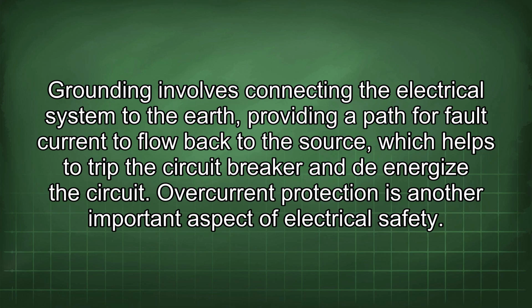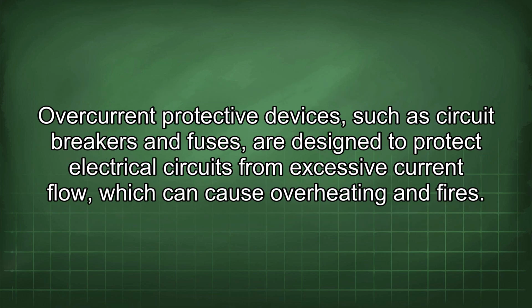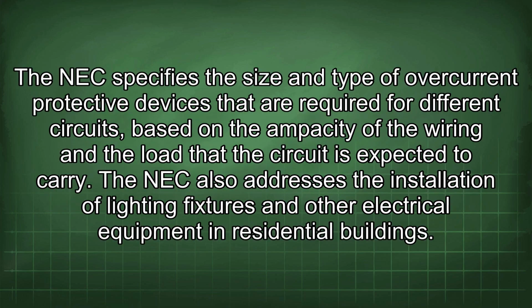Overcurrent protection is another important aspect of electrical safety. Overcurrent protective devices, such as circuit breakers and fuses, are designed to protect electrical circuits from excessive current flow, which can cause overheating and fires. The NEC specifies the size and type of overcurrent protective devices that are required for different circuits, based on the ampacity of the wiring and the load that the circuit is expected to carry.